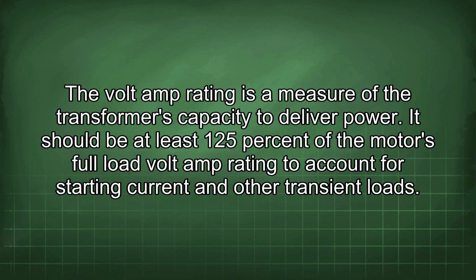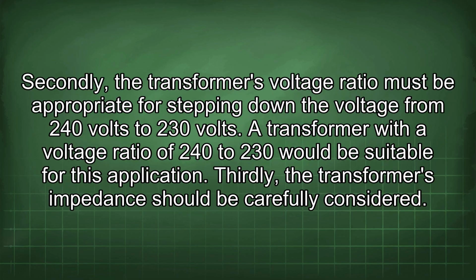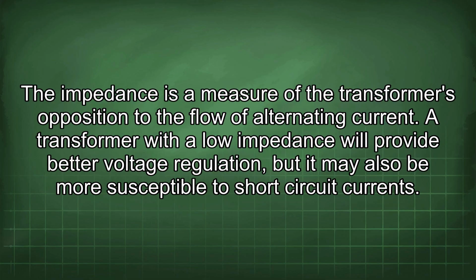other transient loads. Secondly, the transformer's voltage ratio must be appropriate for stepping down the voltage from 240 volts to 230 volts. A transformer with a voltage ratio of 240 to 230 would be suitable for this application. Thirdly, the transformer's impedance should be carefully considered. The impedance is a measure of the transformer's opposition to the flow of alternating current. A transformer with a low impedance will provide better voltage regulation, but it may also be more susceptible to short-circuit currents.